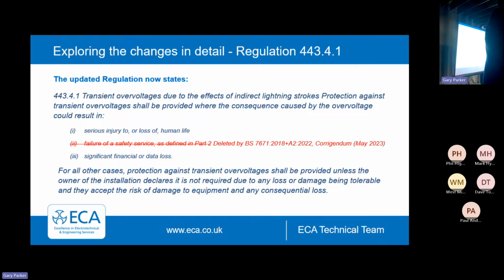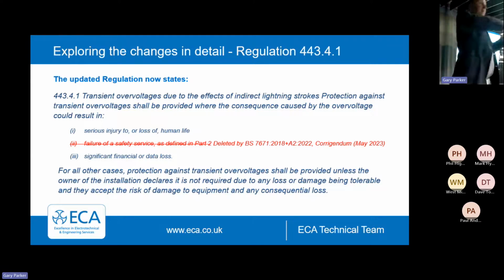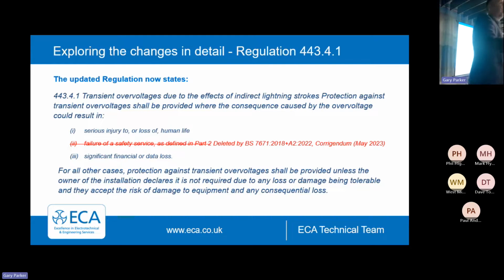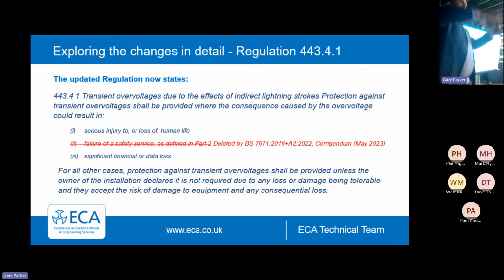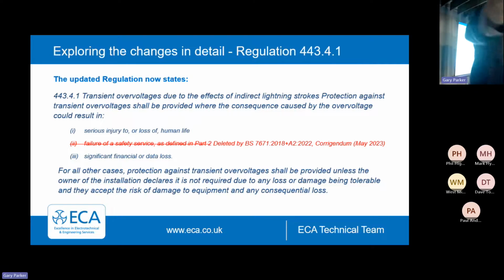As you say, type 1 typically goes at the origin - potential bonding SPD it's called. You normally stick them where you've got a lightning protection system. Then you have multiple type 2s throughout the system. You can get combinations that work here, there and everywhere, placed at different boards, and then you put type 3s on sensitive small bits of kit.